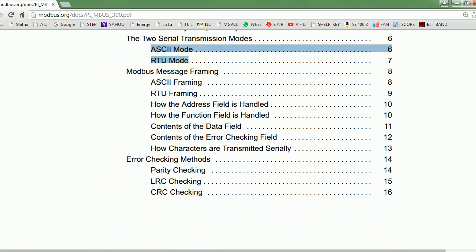Modbus has two types of protocol. One is ASCII - ASCII is not very popular. We'll be using RTU. ASCII has a full set of characters, meaning all 127 seven-bit values are occupied, while RTU uses only hex numbers. When you say Modbus, you mostly mean Modbus RTU. We will be taking Modbus RTU in our case.